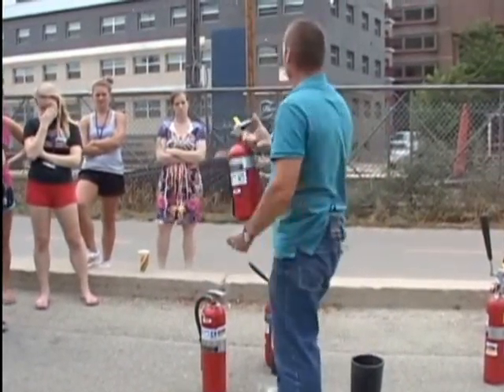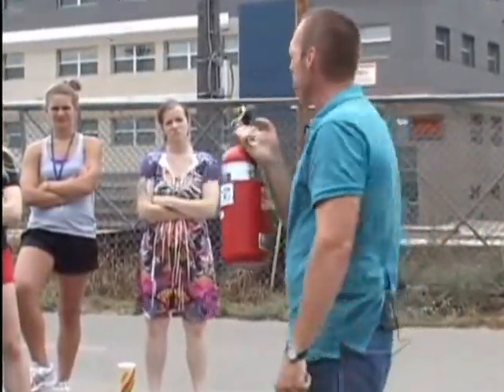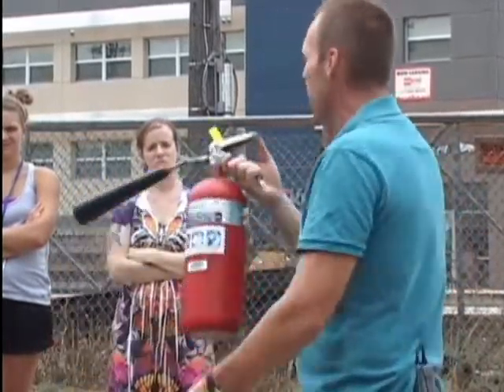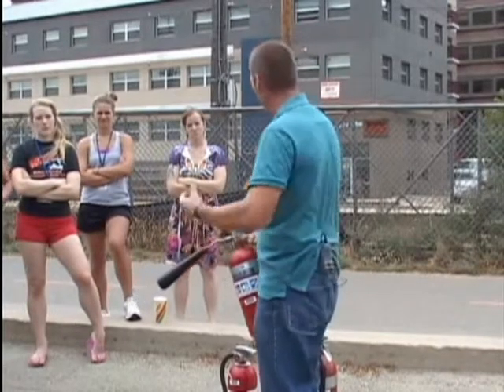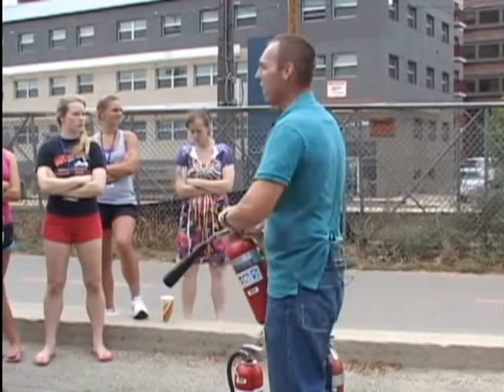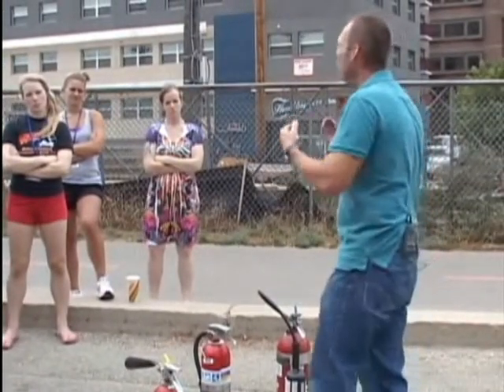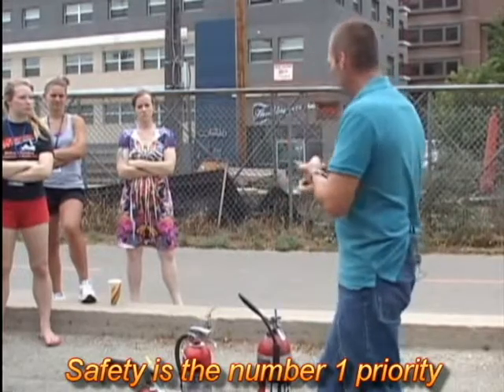When using a carbon dioxide extinguisher, you do the same thing — pull the pin, aim, squeeze, sweep. One key difference: because it comes out as CO2 gas, the five-pound extinguisher is designed as basically a one-handed operation. Do not grab the horn, because as the CO2 comes out it creates dry ice and the horn will frost up. Keep the horn up and in position, then pull, aim, squeeze, and sweep back and forth. Inside, these work great. Outside, because it is a gas it can dissipate, so they don't work as well and you may need to get a little closer. Once the fire is out, back away; if you can't get it out, use that safe exit, close the door, and get out safely.